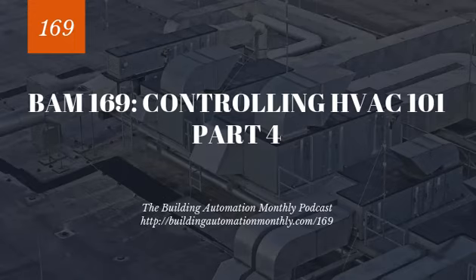So heat transfer, we use kind of 2 ways of transferring heat from steam. Directly utilizing coils called 1/3 and 2/3 coils in an air handling unit. These are large air handling units, maybe 100% outdoor air in environments that have low ambient conditions, and we fire the 1/3 first, and then the 2/3 coil second. So that's 1/3 of the capacity and then 2/3 of the capacity.